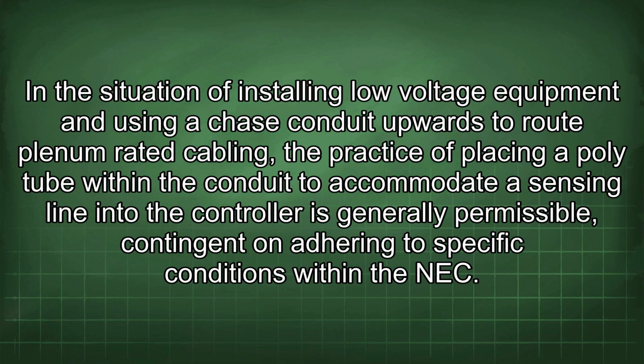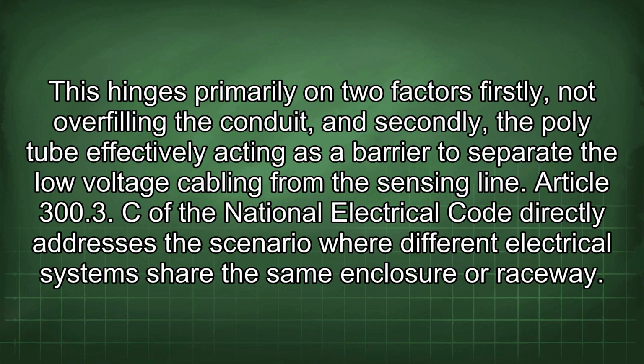In the situation of installing low-voltage equipment and using a chase conduit upwards to route plenum-rated cabling, the practice of placing a polytube within the conduit to accommodate a sensing line into the controller is generally permissible, contingent on adhering to specific conditions within the NEC. This hinges primarily on two factors: firstly, not overfilling the conduit, and secondly, the polytube effectively acting as a barrier to separate the low-voltage cabling from the sensing line.